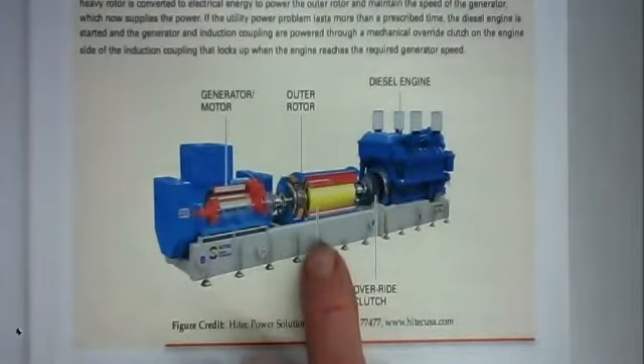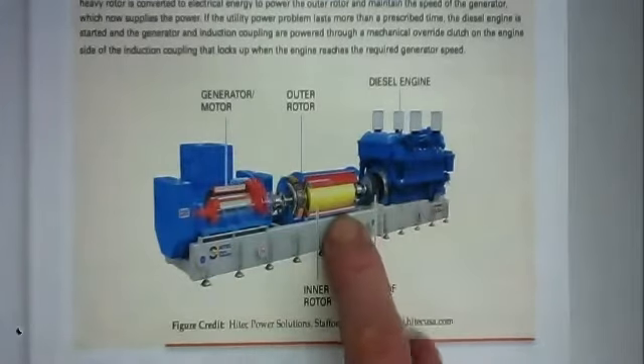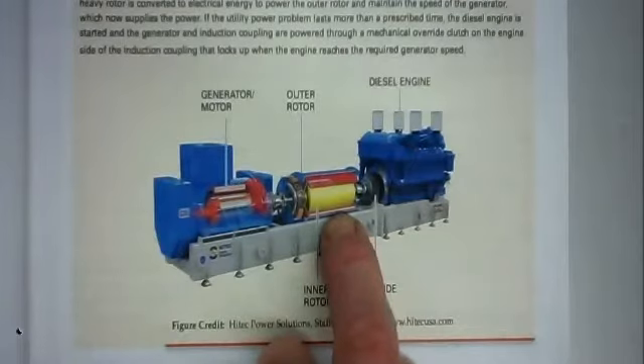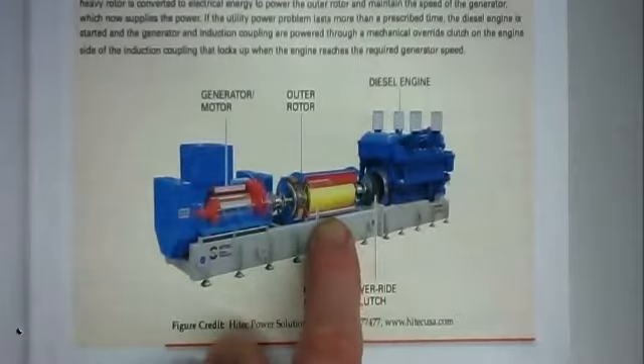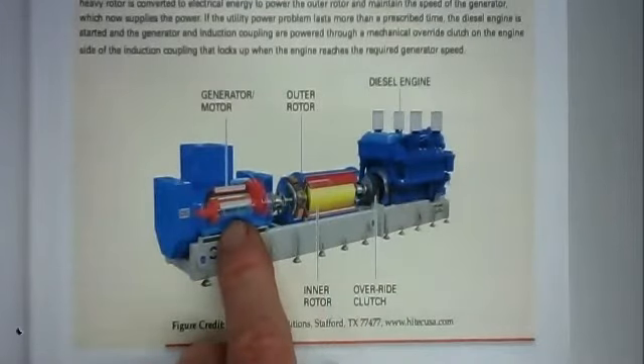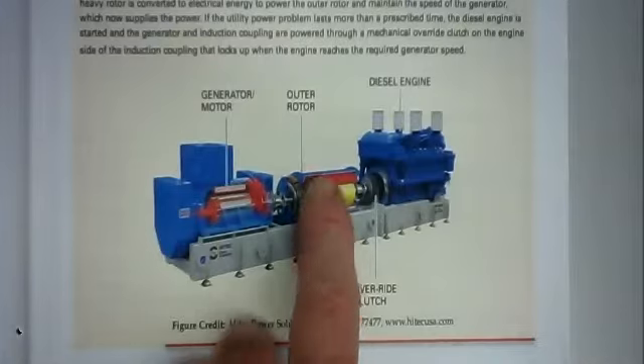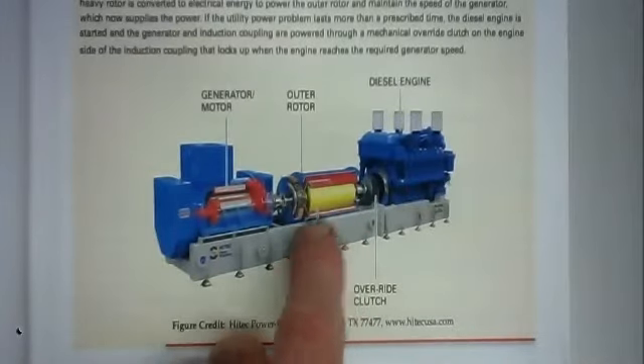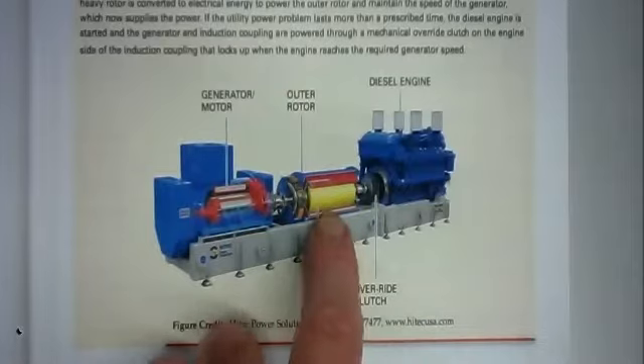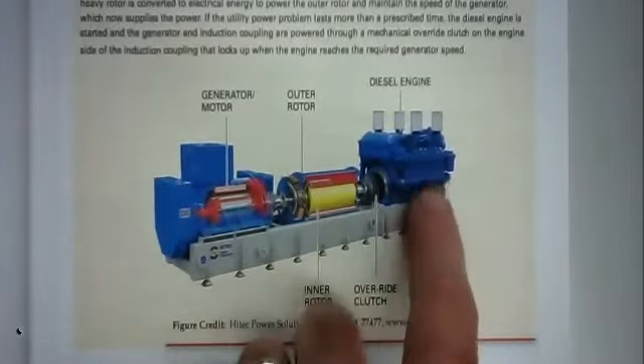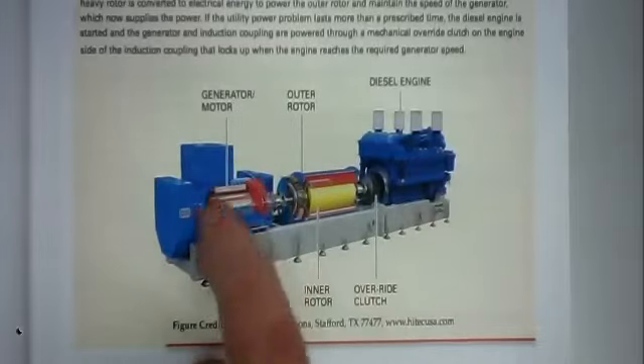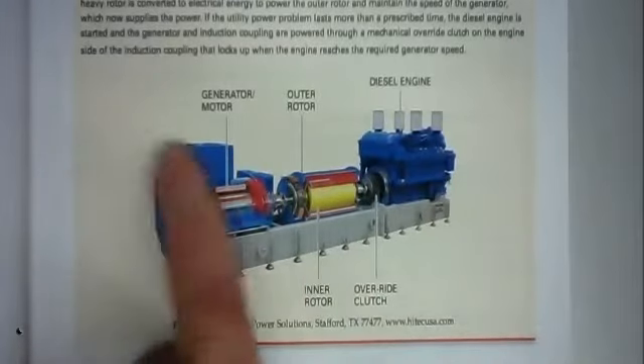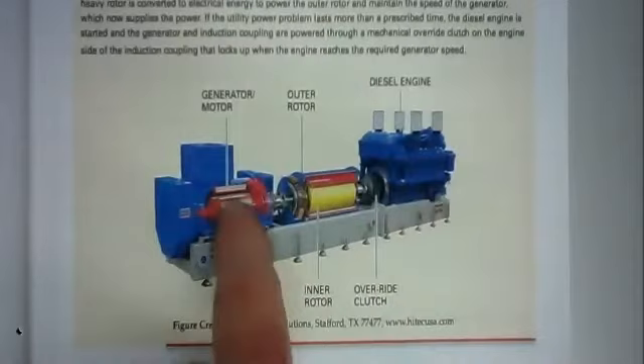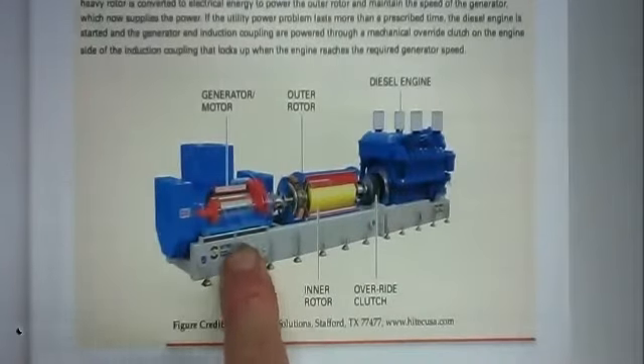So the way this works is the diesel generator is turning this rotor. Like I say, it's about 4,000 pounds. Once you get it going, it doesn't want to stop. And it generates power, and then there's no fluctuation. Once this thing is up to speed, it's not going to just stop on a dime. It's going to keep on going. And that way they can have power while they're transitioning from utility to generator or from generator to utility. This gives them a lot better quality of changeover.